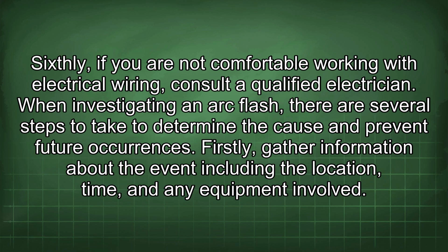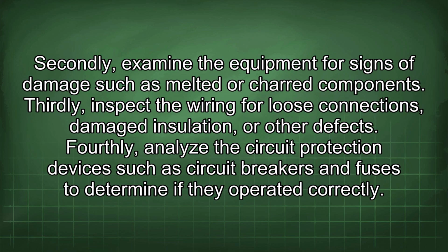Firstly, gather information about the event, including the location, time, and any equipment involved. Secondly, examine the equipment for signs of damage such as melted or charred components. Thirdly, inspect the wiring for loose connections, damaged insulation, or other defects. Fourthly, analyze the circuit protection devices such as circuit breakers and fuses to determine if they operated correctly.